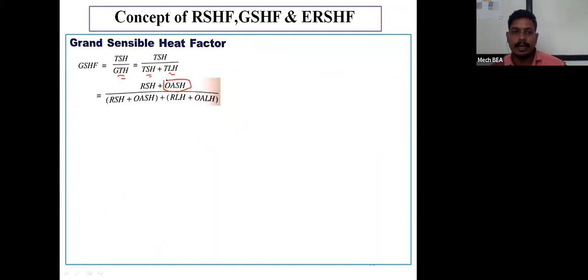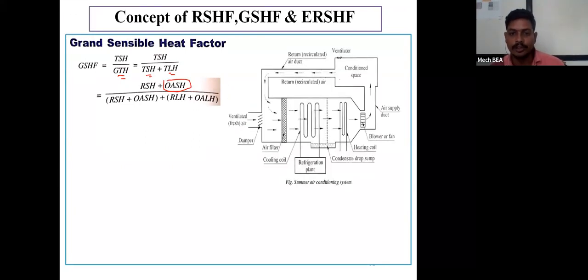Because in the air handling unit, we are mixing the fresh air inside the recirculated air. Whatever recirculated air will be there, that recirculated air will have the condition of supply or required room condition. But the fresh air we are mixing will consist of sensible heat as well as latent heat, which will be different from the required room condition.